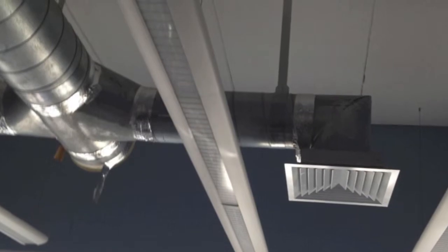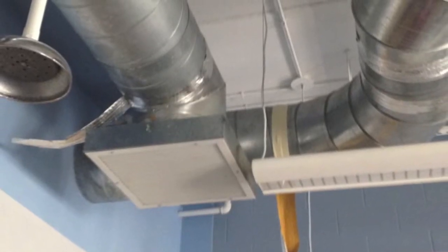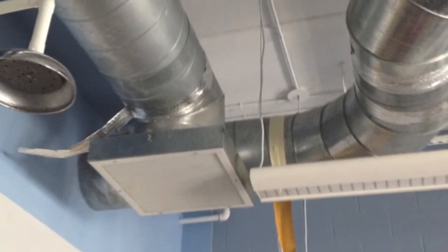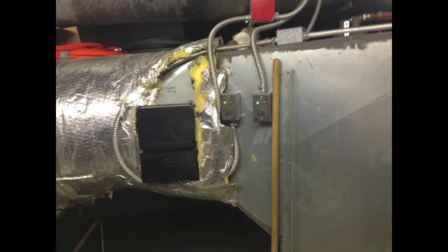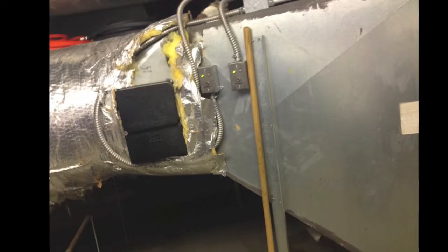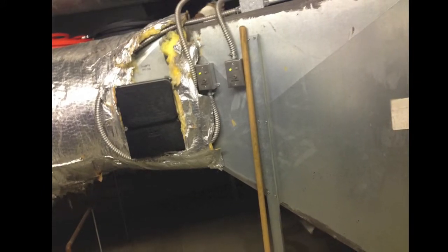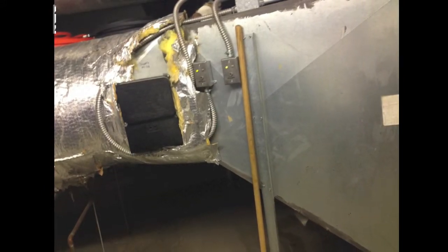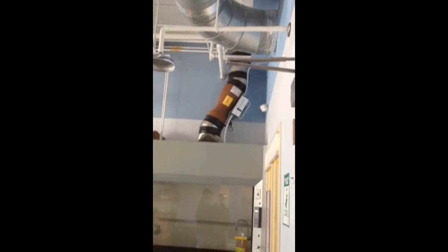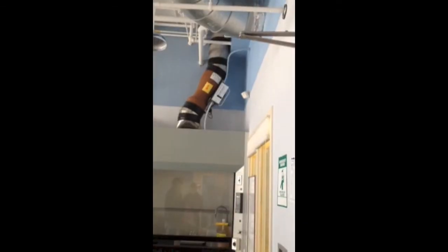Two-thirds of all energy consumed by the Rubenstein laboratory is due to air ventilation. The largest energy-reducing component amongst the proposed upgrades stems from the two HVAC systems, designed to significantly decrease airflow rates and system pressure. Right now, we're just ventilating the space. No one's in here. And this building was designed with sensors to have occupancy and unoccupancy set points.